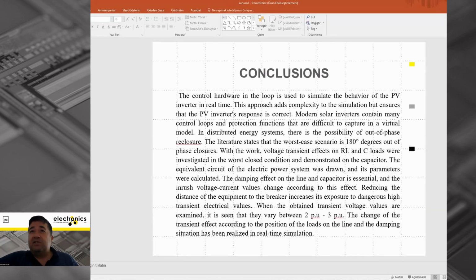The controller hardware-in-the-loop simulation is popular recently and is used to simulate the behavior of the PV inverter in real time. Again, our PV inverter is a physical inverter, a real inverter, and we put it in the simulation. This is an important aspect. This approach adds complexity to the simulation, but ensures that the PV inverter's response is correct. Modern solar inverters contain many control loops and protection functions that are difficult to capture in a virtual model.